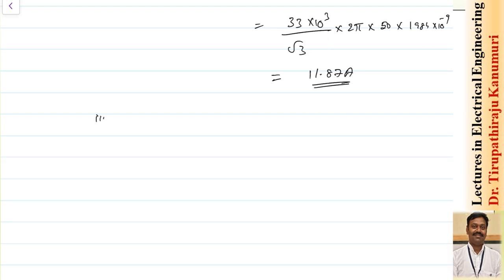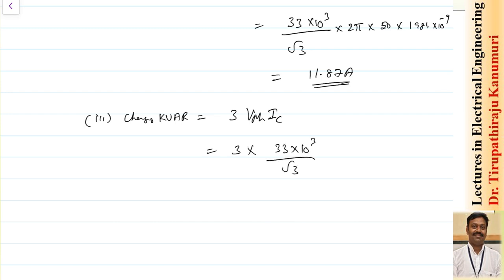Total charging kVAR = 3 × Vphase × charging current per phase = 3 × (33 × 10³/√3) × 11.87, which equals 678.5 kVAR. Because there are 3 cables (3-phase), we multiply by 3; for a single-core cable, you would take only 1.